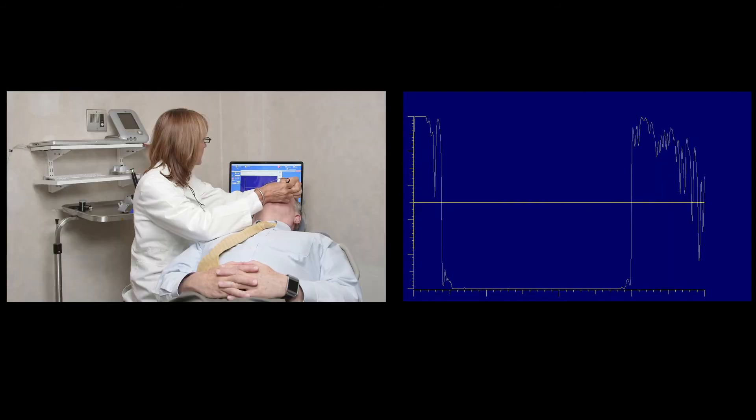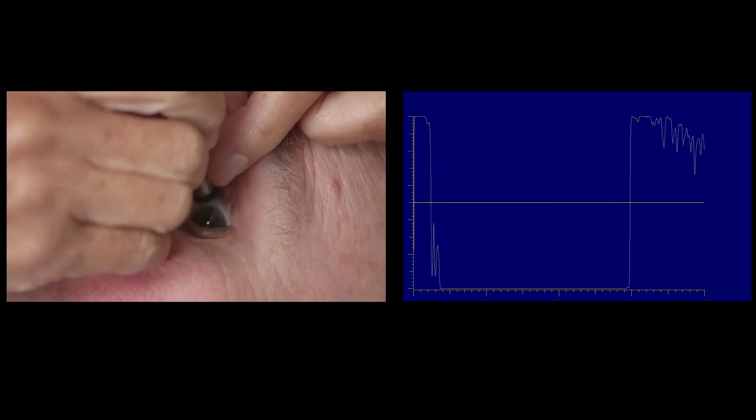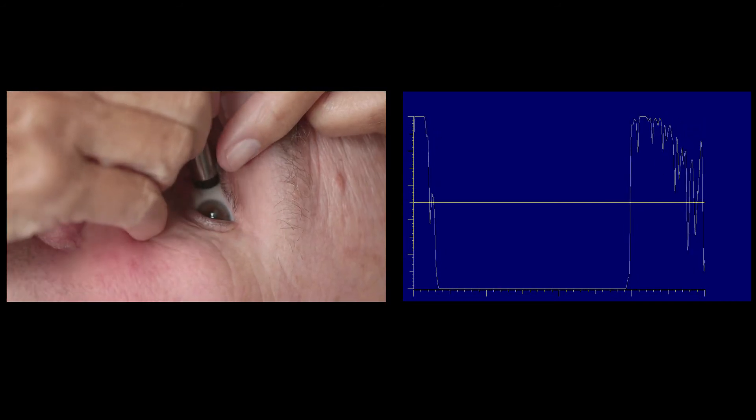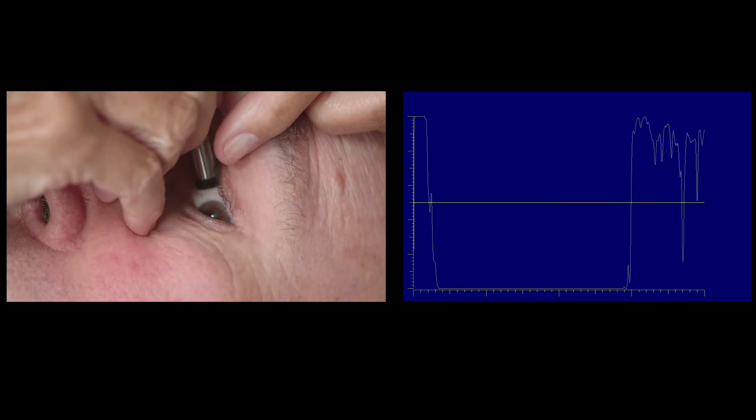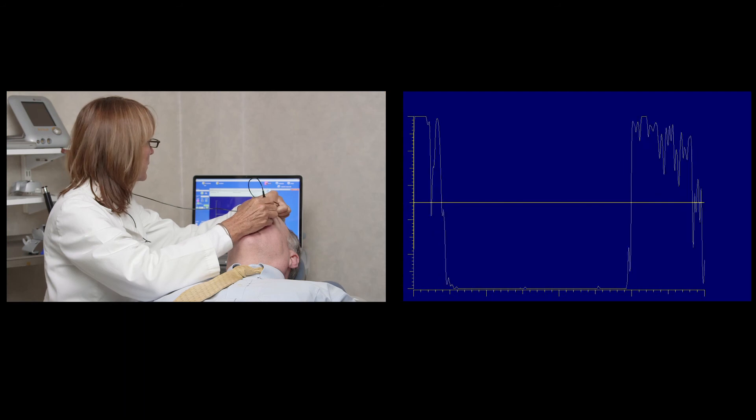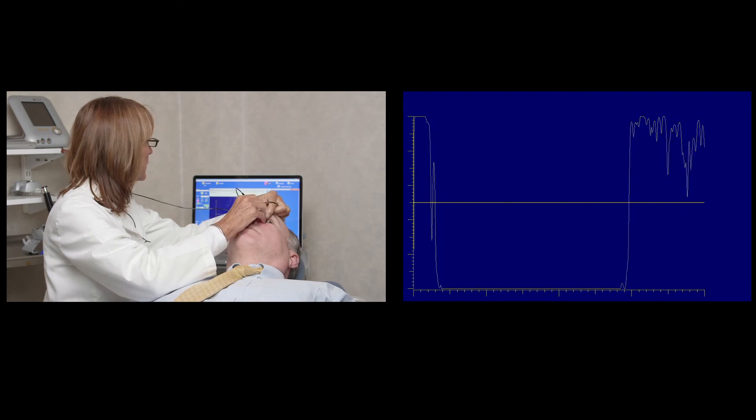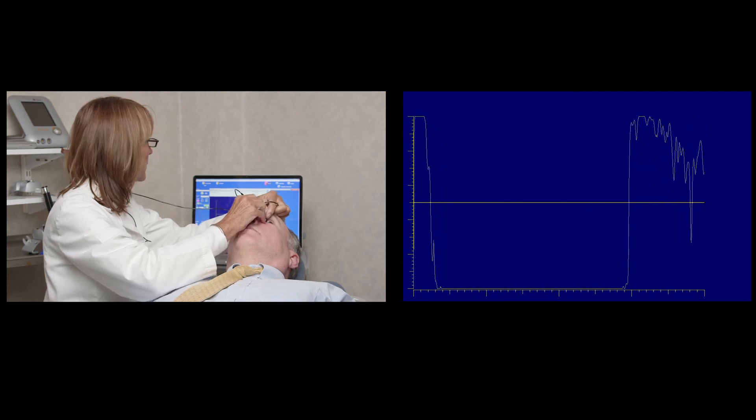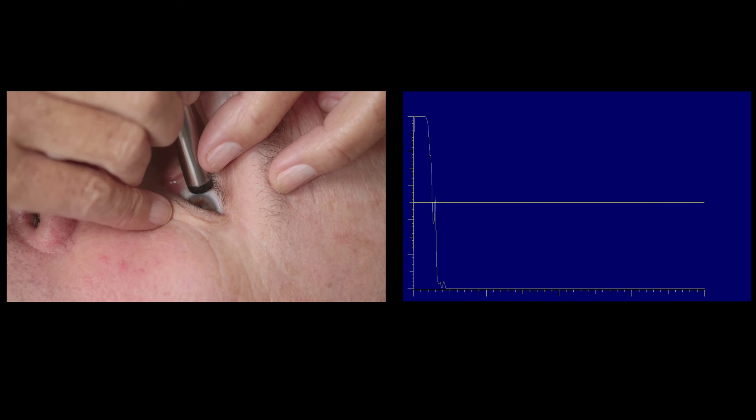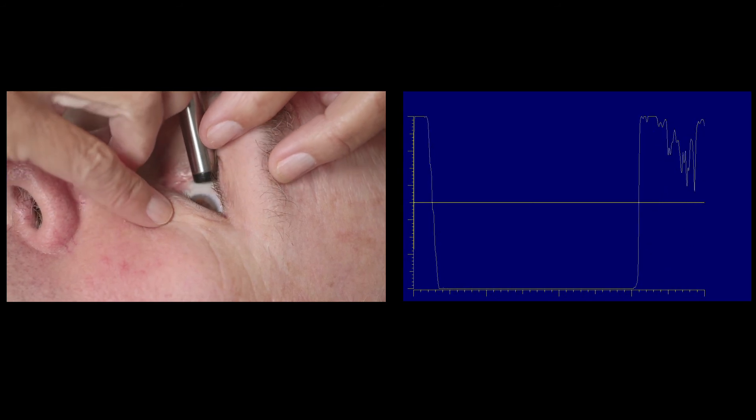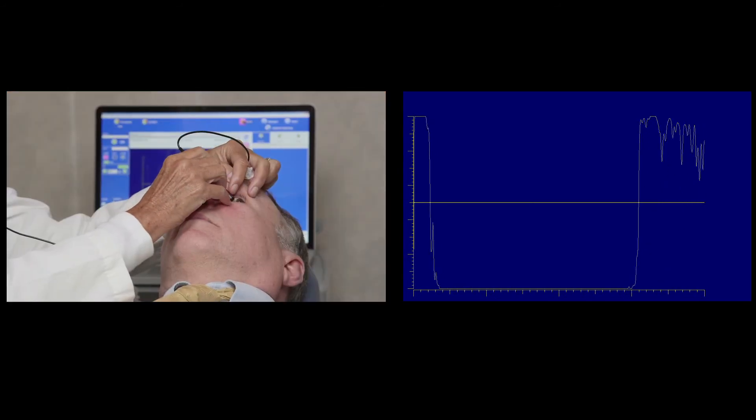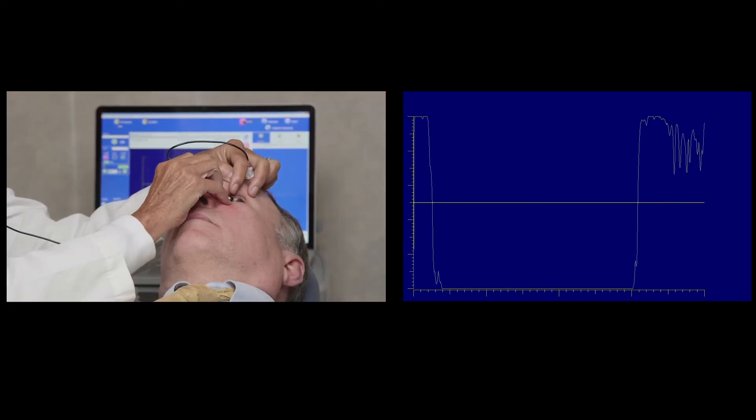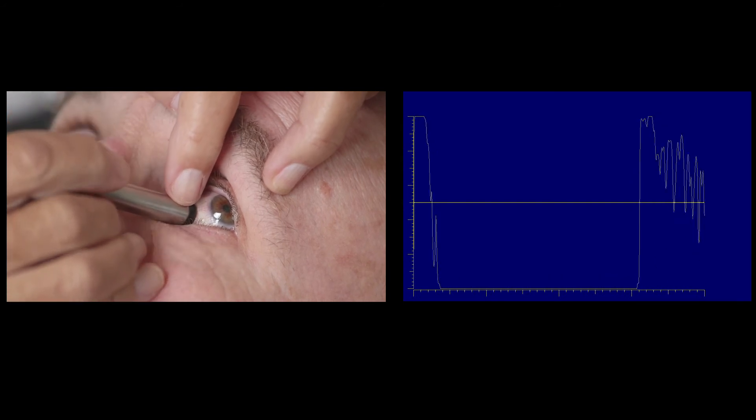It is important to maintain perpendicularity of the sound beam. In addition to transmitting ultrasound waves, the probe must also be able to receive their reflections, which occurs optimally only when the sound beam is perpendicular to the area of interest. The more the probe's angle of incidence diverges from the perpendicular, the less reliable the image will be.